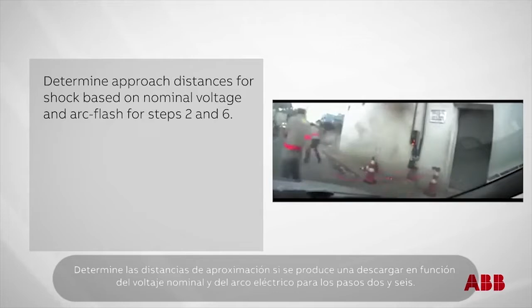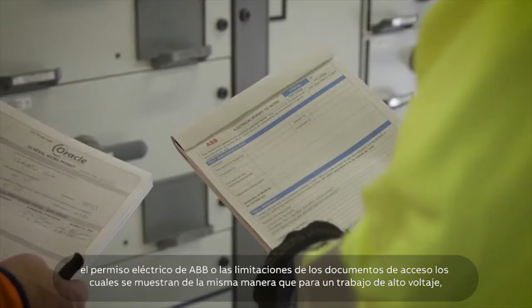Determine approach distances for shock based on nominal voltage and arc flash for steps 2 and 6. Decide on appropriate work methods and finally, initiate the permit to work process. Remember, a permit to work is not always issued for low voltage work. In the absence of any other control document, an ABB electrical permit to work or a limitation of access document shall be utilized, and used in the same manner as you would for high voltage work. By adopting this same process, there is less chance of anything being missed or overlooked, and a consistent approach can be applied to electrical work at any voltage.